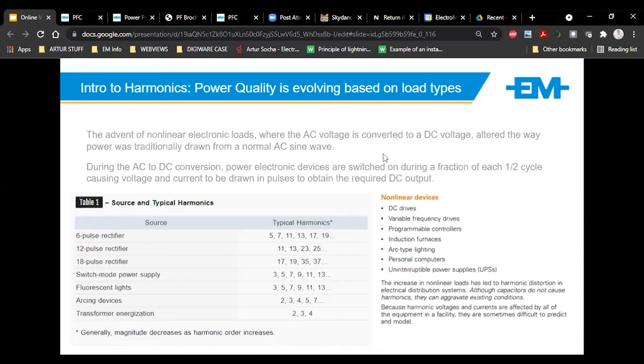So it's just an example of different sources. A VSD, you get 6 pulse, 12 pulse, 18 pulse. The more pulses, obviously the better the drive is, but it's going to cost you a lot more. Typically, it's all 6 pulse VSDs out there.